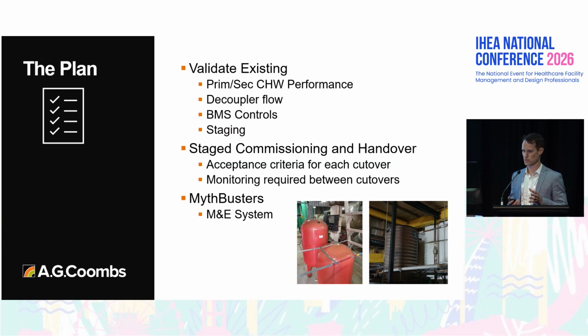A big focus before we even started ripping plant out was the staged commissioning and handover process and the commissioning management side of things. We made sure there were clear acceptance criteria for each cutover so we had confidence that before we moved on, everything was reliable and stable and could be left in place. That included making sure we had time between stages to watch it operating with the existing plant before we cut over the next chiller.